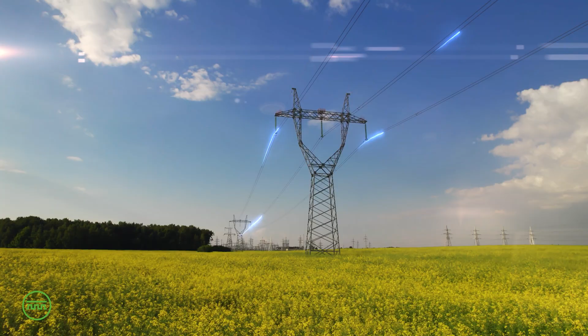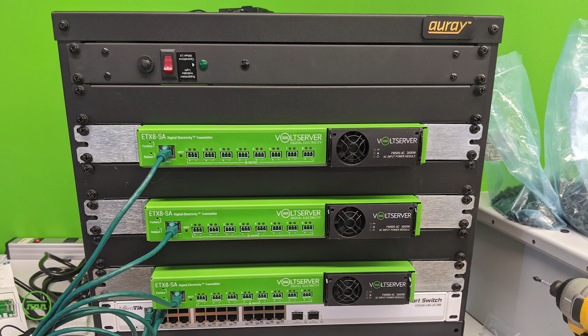That's why fault-managed power systems were born. These systems enable power to be faster, more flexible, more manageable, more controllable, and safer than conventional electricity. They're also much easier to deploy, which can significantly reduce project costs and allow fast device setup and powering. Unlike conventional electricity distribution, the inherent safety of fault-managed power systems means that they can be installed using low-voltage installation practices. Fault-managed power also minimizes electrical hazards.